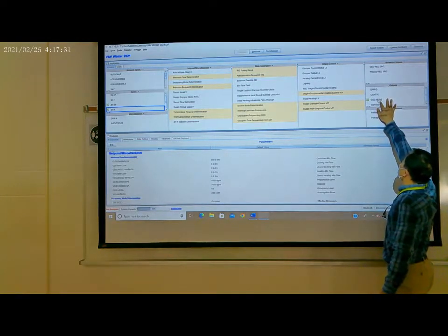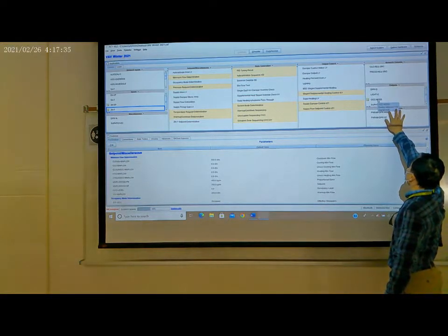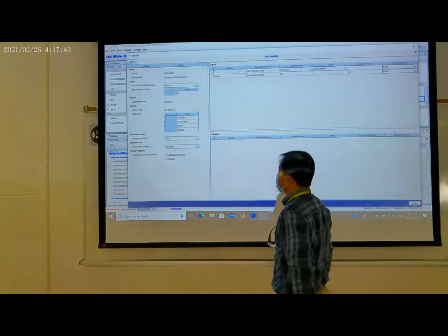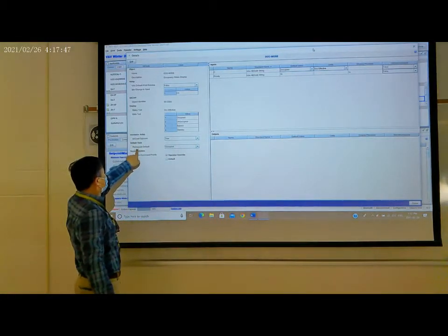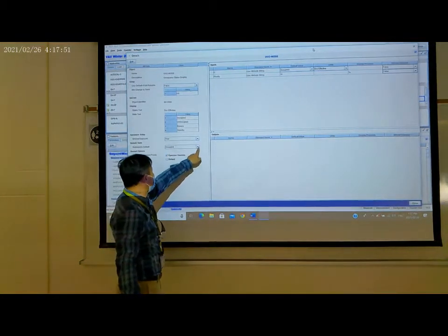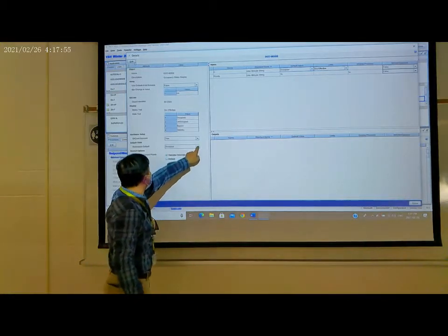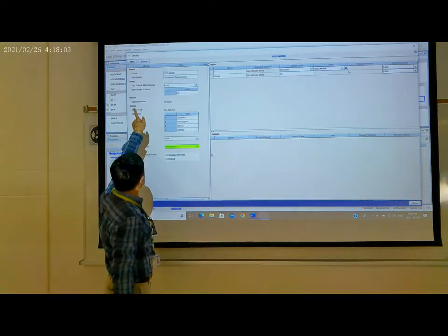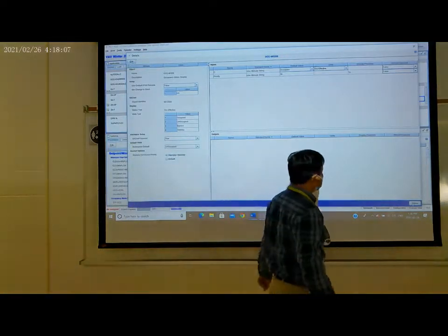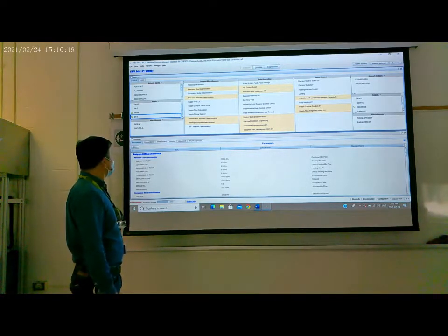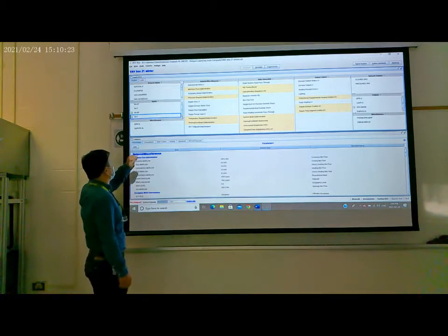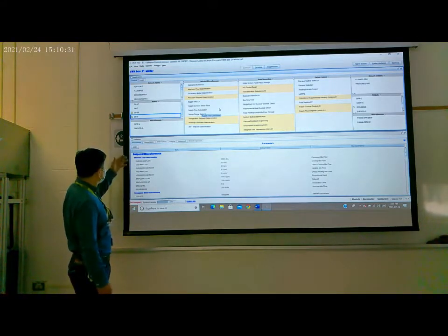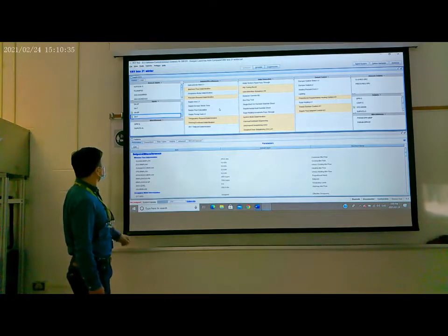And the output here, we said that this is an occupancy mode. This is SA bus, so it's okay. So double click. Here, the default state is occupied. We should set unoccupied. We should set the note here. And then unoccupied, this one. Set this one, and then apply, and then close. Okay, now we complete the setting for the supply air temperature, zone temperature set point and zone temperature sensor. We complete the setting for the input.